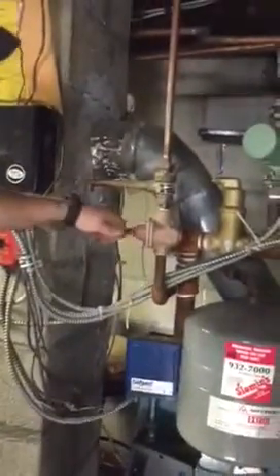That main one down here is the return isolation valve. Each individual supply has an isolation valve. Open the feeder one first. If you don't hear anything, lift the lever to manually feed the boiler. Once you reach around 10 to 18 PSI, open up all your valves and you should be good to go.